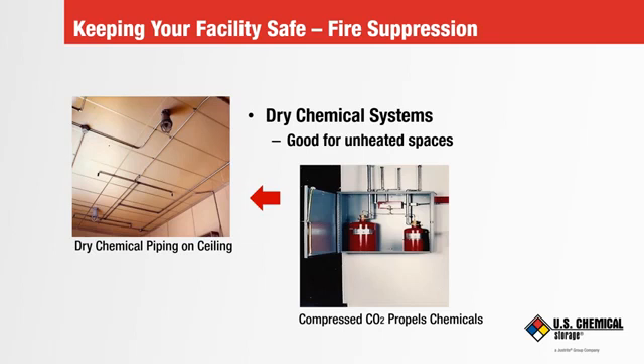Now, there is commonality with all fire suppression systems, and there's more than just sprinkler and dry chemical. But they're all common in that they can trip a fire alarm and turn on a local audible and visual alarm strobe on the roof, as we just saw, and send a signal to a facility's central guardhouse, and it can automatically, or they can manually, send that signal on down to the fire department.